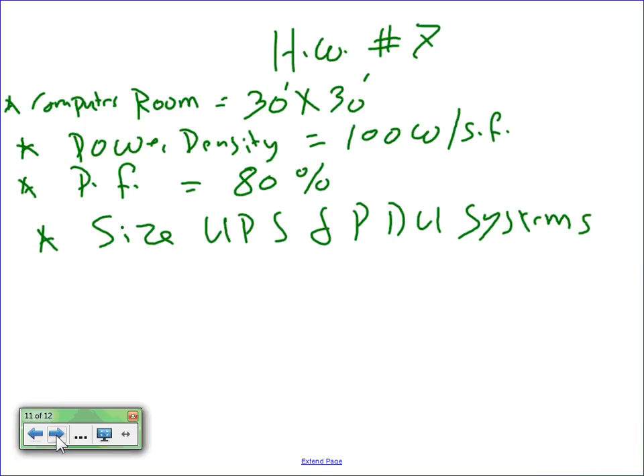Okay, the last thing, guys, will be homework number 9. Please change this one into homework number 9. Homework number 9 is the following. I have a room of 30 by 30, a square room. I want to put servers in it, and I talked to the computer engineers like Chris, and they told me that the density that we can rack in that baby is 100 watt per square foot, not 30, 100. The power factor assumption, I'm going to continue worst scenario 80. And I need to size the UPS and PDU system. Basically repeat the 5 steps or the 6 steps for the PDUs and the UPS.